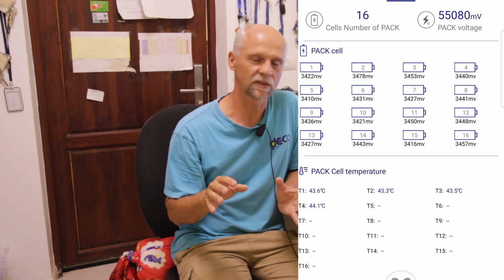Because if you only allow balancing during charging, you are missing out on a very important time frame, and that is when the battery is full and individual cell voltages might be on the high side. Once the charging is done and you stop balancing, you're missing out on that time where you could continue and balance those high cells, draw the voltages down.